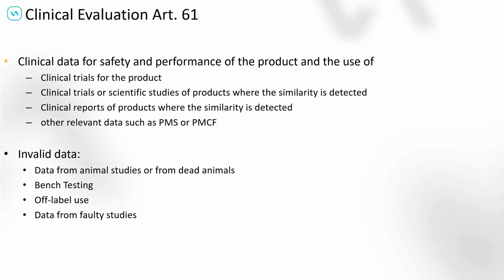It's not possible to utilize bench data for Article 61, unless there's one exception I can tell you later. Bench testing data, since it is technical data, does not work. Data from animal studies or cadaver studies does also not work for clinical trial data and clinical data safety. Also, if the study does not fulfill ISO 14155, or has no ethics committee vote, so bioethics vote, if the study is formally not correct, then you will have issues utilizing those articles in the clinical evaluation.